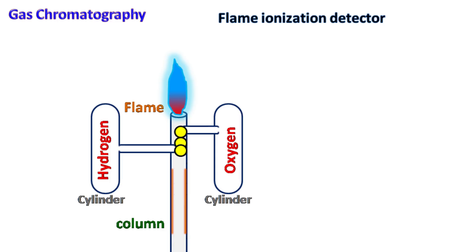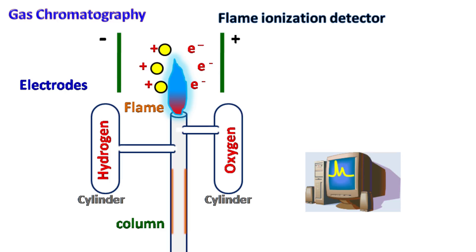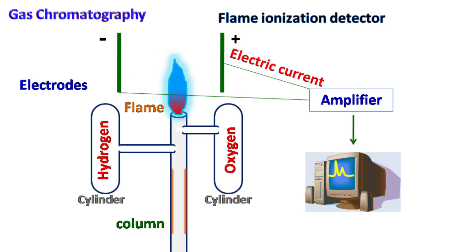When the sample molecules reach the flame, they get ionized and the electrons are released across the flame. There are two electrodes, each with a positive and a negative charge. The electrodes detect electrons generated by the ionization of the sample. Electrons are detected in the form of current which is amplified and detected by the computer.